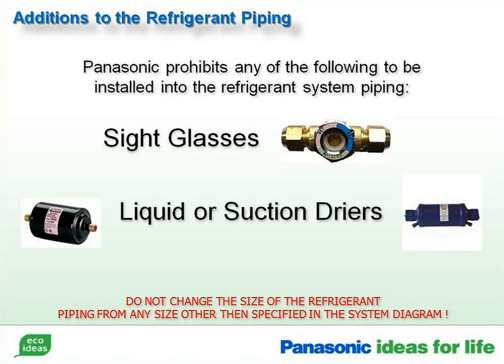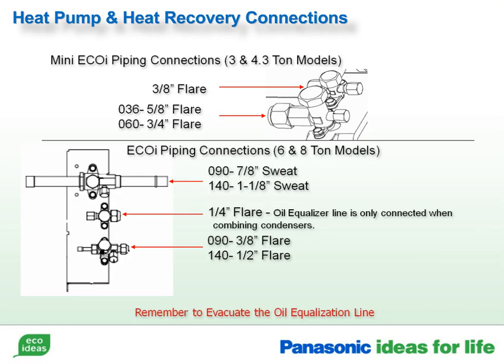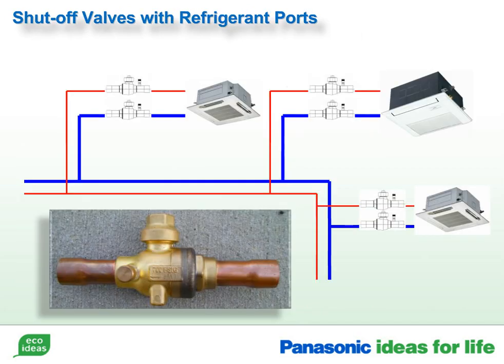Do not use dryers or sight glasses. Dryers can temporarily be installed in a contaminated system, but they should be removed once the system has been cleaned. Dryers should be correctly sized and rated for use with R410A and POE oil. Condensers will be sweat, flare, or a combination of the two. Remember to evacuate the oil equalization line when condensers have been combined. When ball valves are used, install the gauge connection port towards the air handler. Remember to open the valves when evacuating the system, and do not forget to remove the Schrader core when brazing.